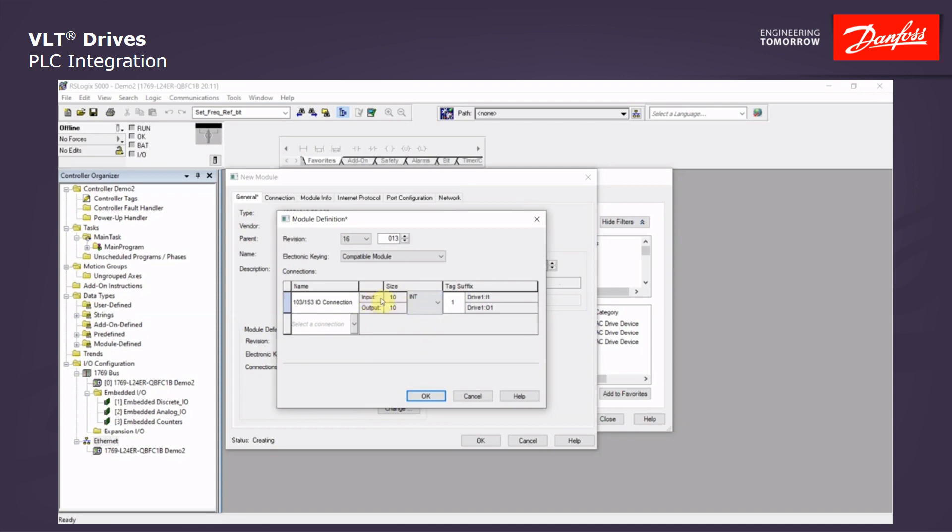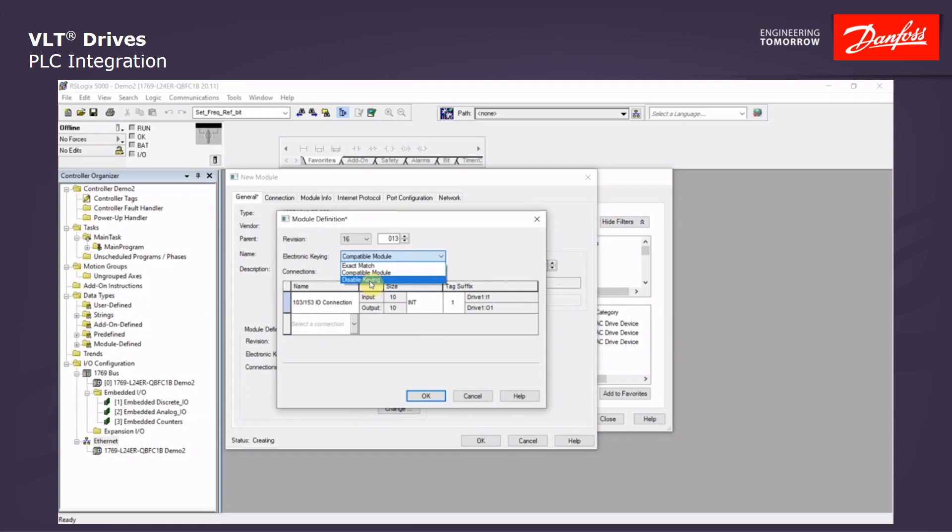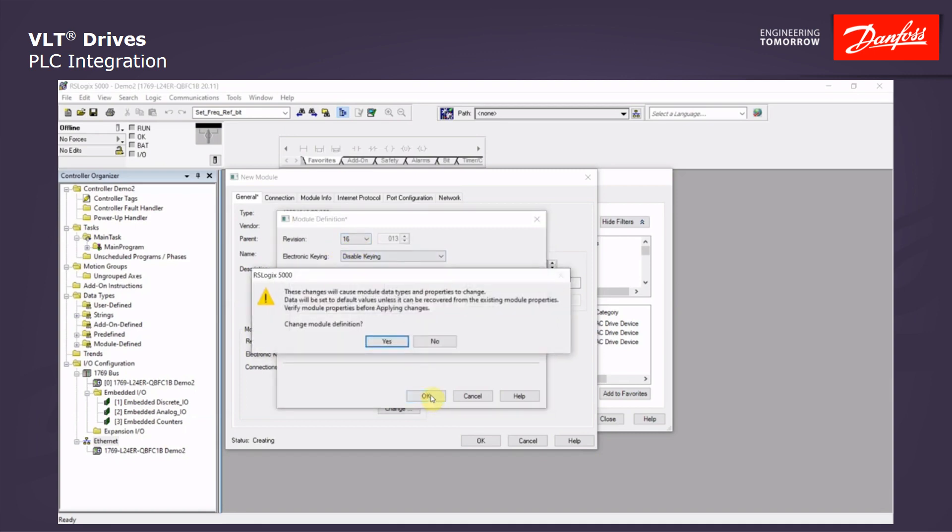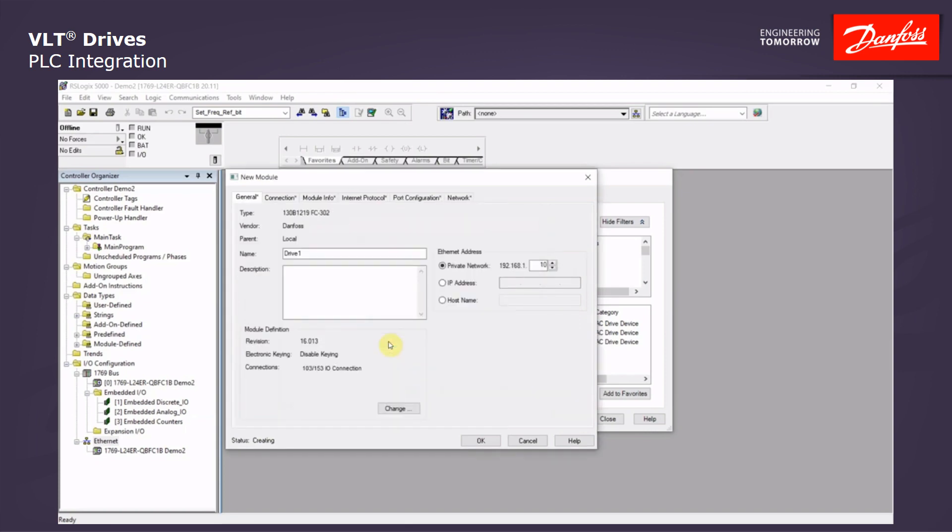And that's where we see the input and output ten integers. At this time, we can also change the electronic keying. The default is the compatible module, which is fine for most installations. But you can disable this keying for future updates so it's not to have an issue with the revisions of the drive. Click OK. Ask if this is OK. Say yes. And OK.